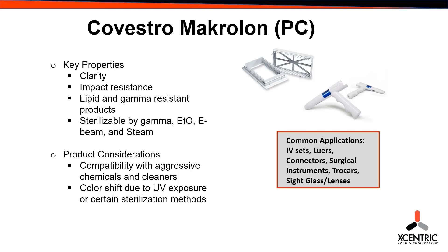While polycarbonate has been in use for over 50 years and has a good safety track record, another thing to take into account with polycarbonate is that it is not BPA free. While there are only very low residual levels, this still needs to be evaluated when considering this material.